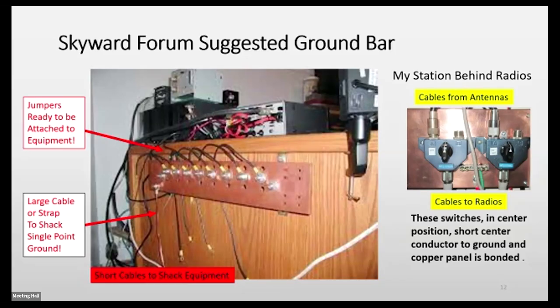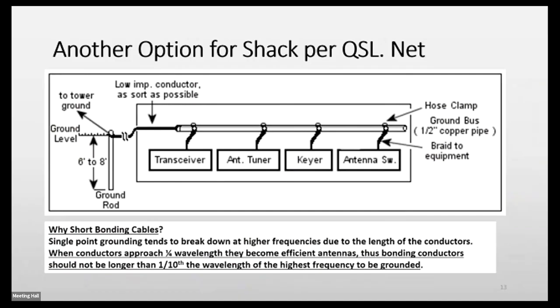Here's another option some people have used. They run a piece of copper pipe across the back of their desk, using straps across there and up to their equipment. This is a top view and side view, and you can see a short length of cable to the ground rod itself, and you've got a tower ground. The only thing about hose clamps is that once in a while you need to go back and retighten them, they like to loosen up, they don't like to stay tight. So it's a good idea, on a preventive basis, to loosen and tighten them again on an annual basis at least. I don't know why, but they don't like to stay tight unless they're on rubber hose, then they do a pretty good job, but you're not tightening on the rubber, you're on metal to metal.